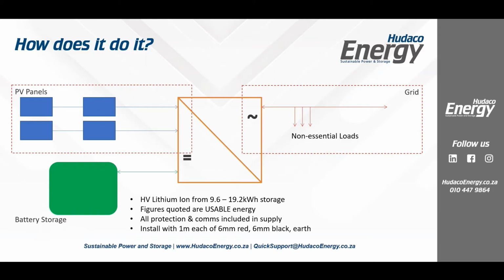I'll show you some pictures of those a little bit later, and the entire installation time is so fast on this. The figures that we've quoted, the 9.6 to 19.2, that is usable energy. That is not capacity. That is usable energy for the client. Certainly the capacity is higher, but the battery management system in the batteries and the inverter are unconcerned about the actual capacity. Rather, they just focus on what is usable.